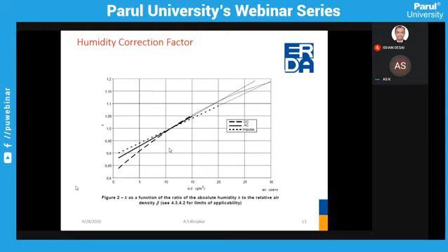Please remember that whatever insulation is directly exposed to the atmospheric condition, where the external atmosphere affects the insulation characteristics of the sample or particular insulation, there we'll have to apply the correction factor. Otherwise, we need not apply the correction factor, like in a transformer.